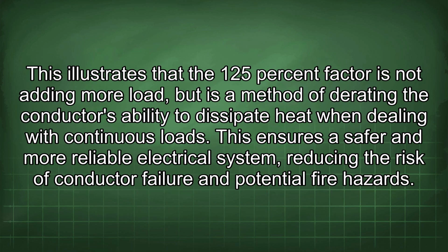This illustrates that the 125% factor is not adding more load, but is a method of derating the conductor's ability to dissipate heat when dealing with continuous loads. This ensures a safer and more reliable electrical system, reducing the risk of conductor failure and potential fire hazards.